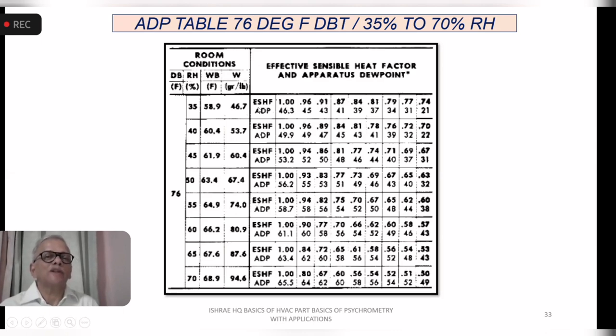Depending on effective sensible heat factor, the ADP is dictated. So you have a table, and you will be able to select the apparatus dew point based on the effective sensible heat factor which you have calculated for the space for the given room design conditions. So that's how they get linked with each other. Now we'll see further what the effects are.